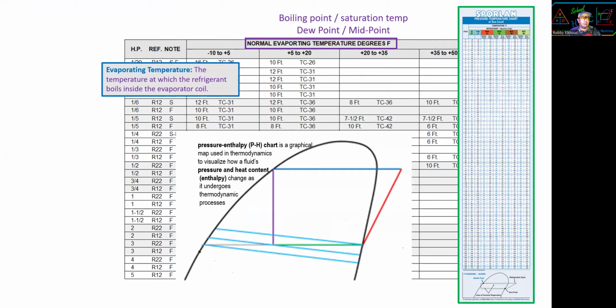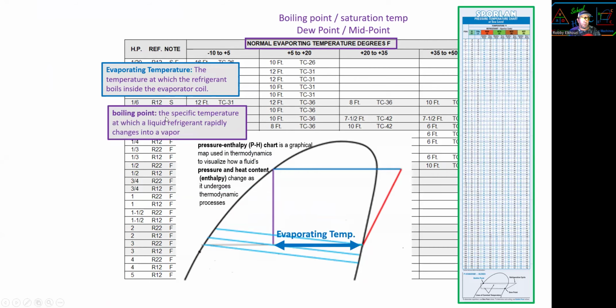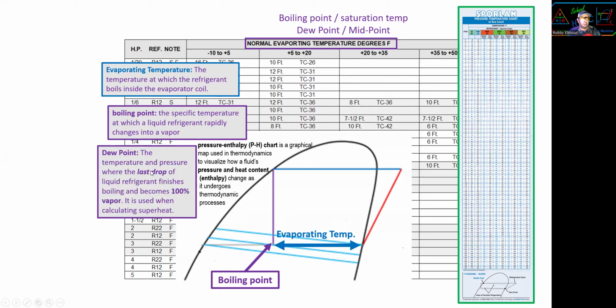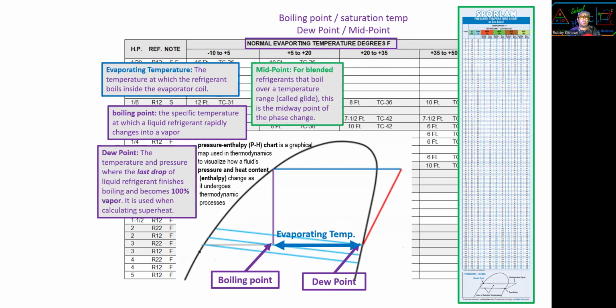I'll explain. Evaporating temperature, the temperature at which the freon boils inside the evaporator. That's your evaporating temperature everywhere in the liquid vapor mix line. The boiling point, the specific temperature where liquid refrigerant rapidly changes to vapor. That's when the boiling point starts. The boiling point is the start of the evaporation temperature. The dew point is the last drop of the liquid refrigerant when it becomes 100% vapor, which is at the end of the evaporation temperature. And then saturation temperature, somewhere in there.